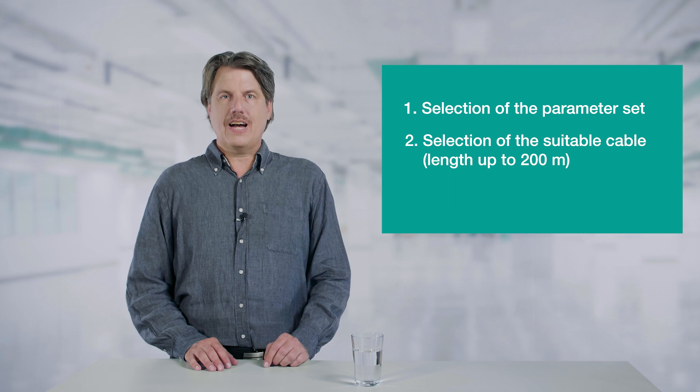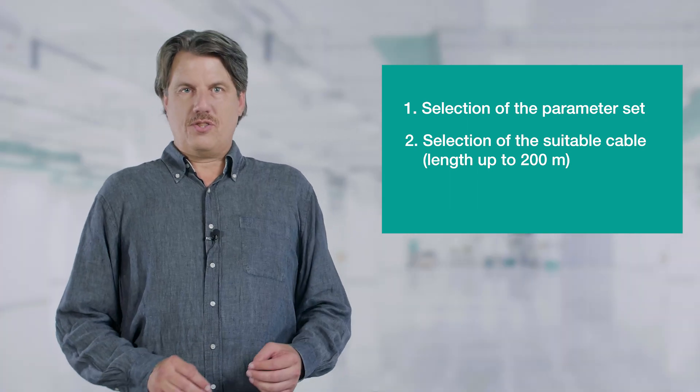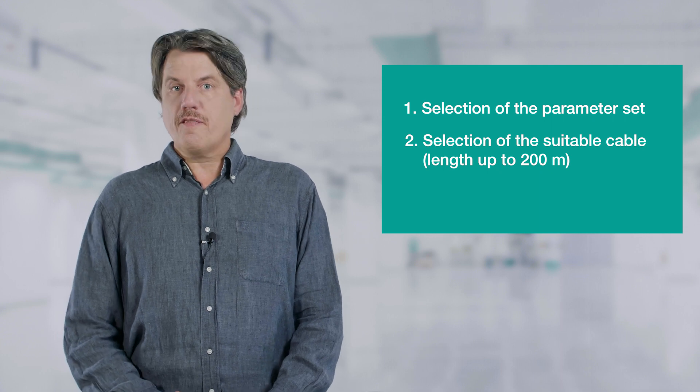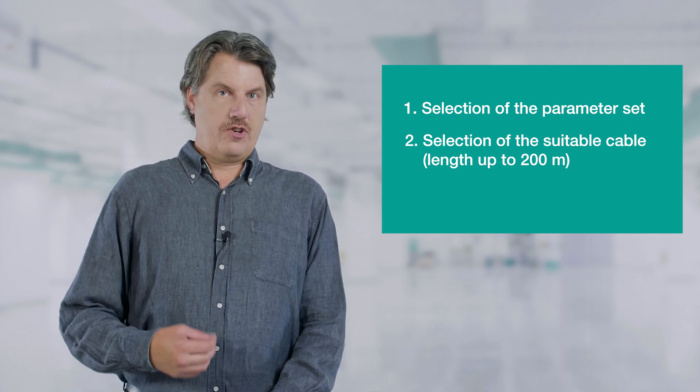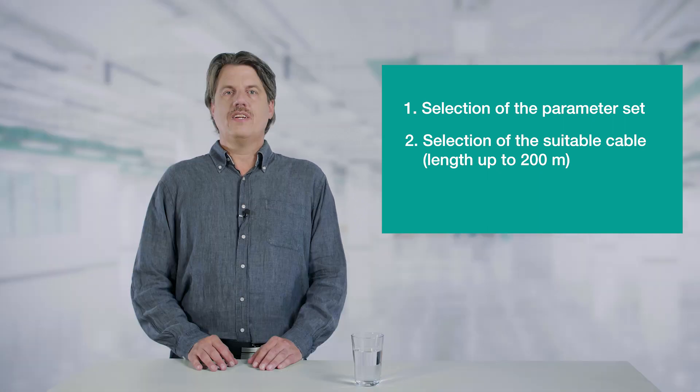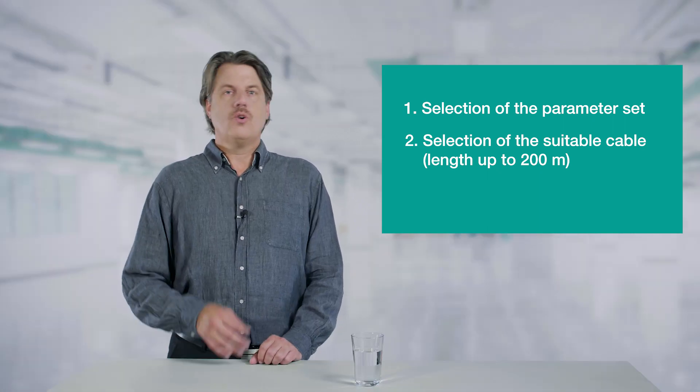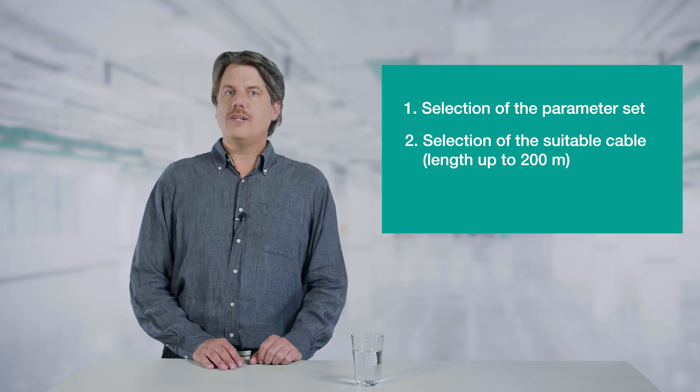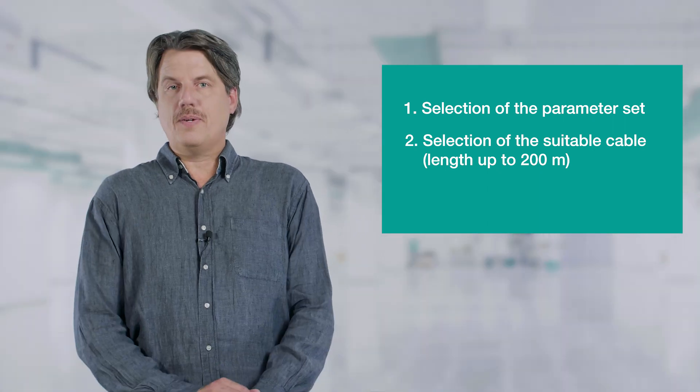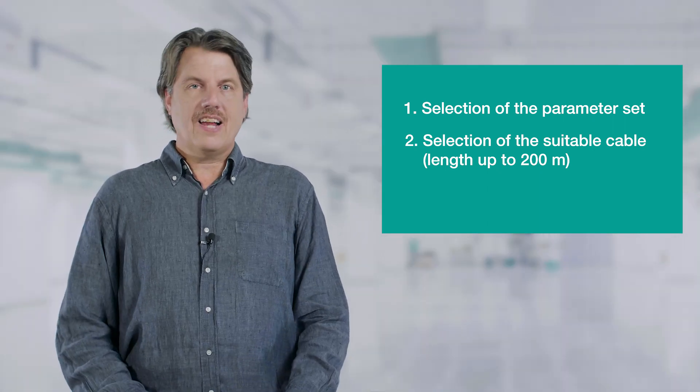Following this, select the appropriate cable. The cable connecting the switch and the field device must also meet certain requirements in terms of resistance, capacitance, and inductance. When selecting the cable, the Type A cable that we already know from the field bus meets these requirements. The cable may be up to 200 meters long.